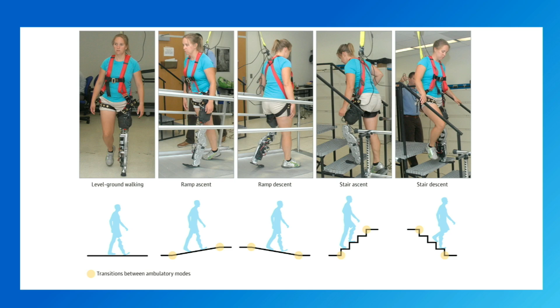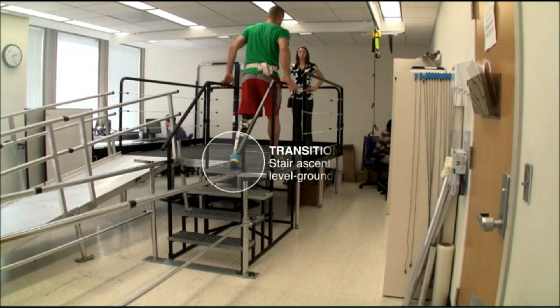So this is an example of what happens, again, one of my cool videos. If it didn't predict right here, the person would have just kicked the step. So it needed to predict the change so that the knee could flex more, so that the person could place it in a location. Similarly here, if it was still in stair climbing mode, it would hang up and he would not be able to bear weight on the device. Going down the steps, if it doesn't predict right here, it's too stiff and the person can jackknife over the device and fall down the stairs.